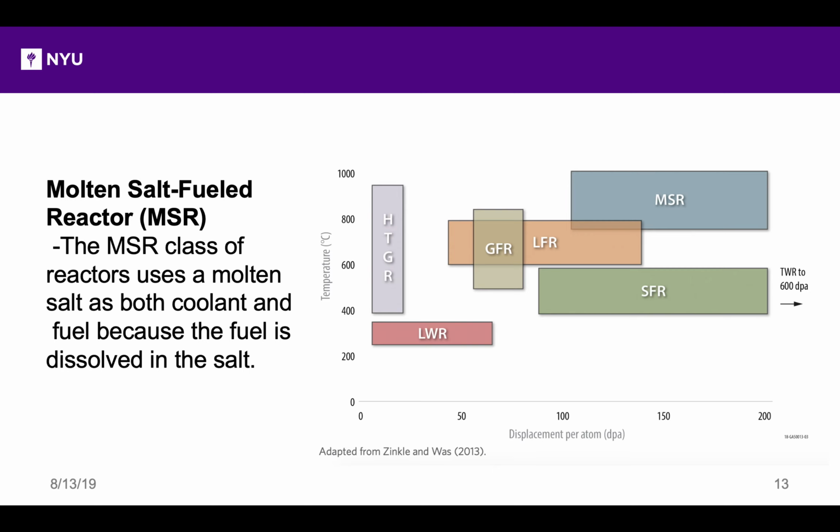Nuclear reactor systems can be compared using key parameters such as operating temperature and the neutron damage to important core structures, such as the fuel cladding, that limit operational conditions. A key metric for the level of neutron damage is neutron-induced displacement of atoms from their original position in the material lattice, which is measured in terms of displacements per atom, dpa. The level of damage is a function of the material being tested, the damage probability, the neutron spectrum, the neutron flux, and the irradiation time.